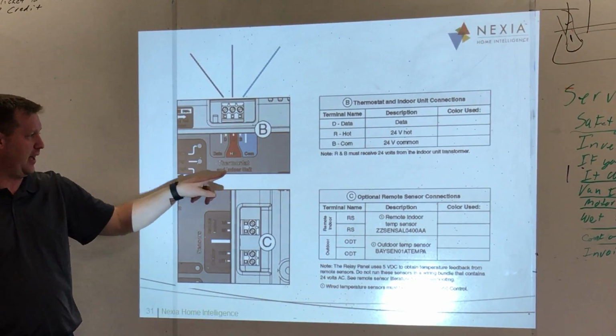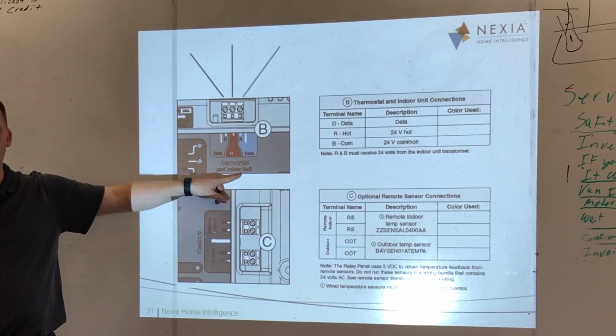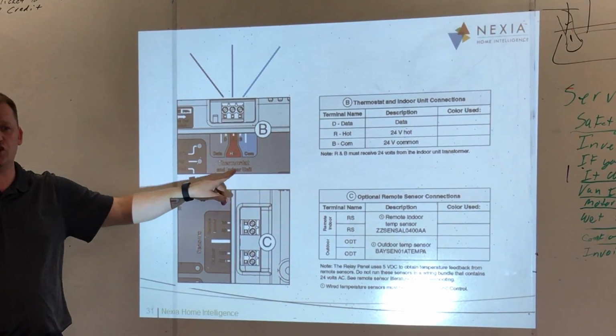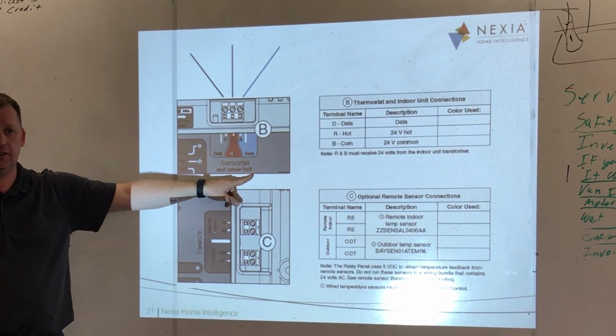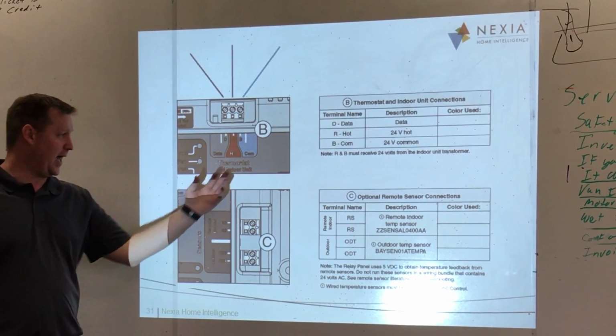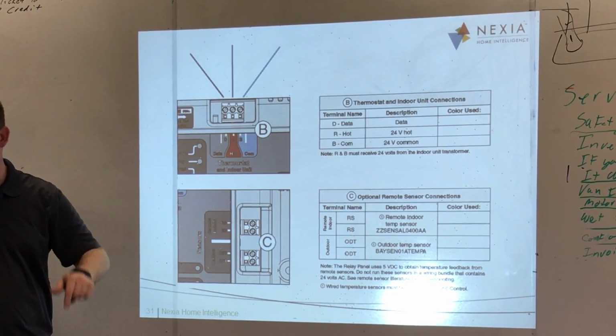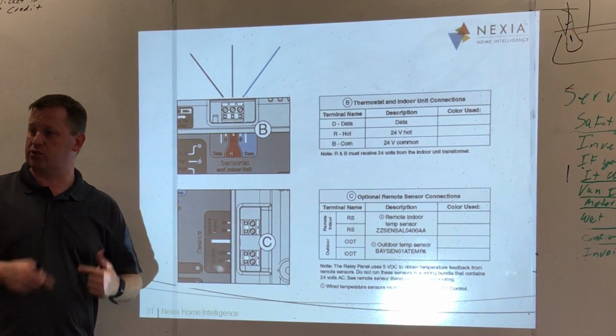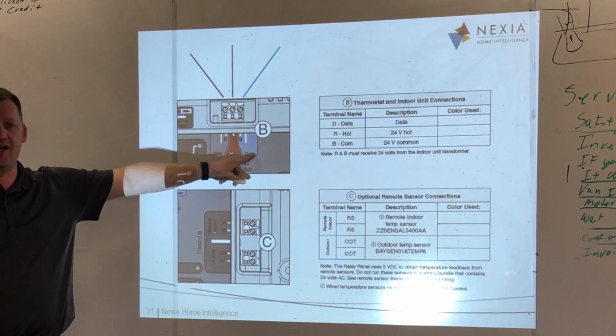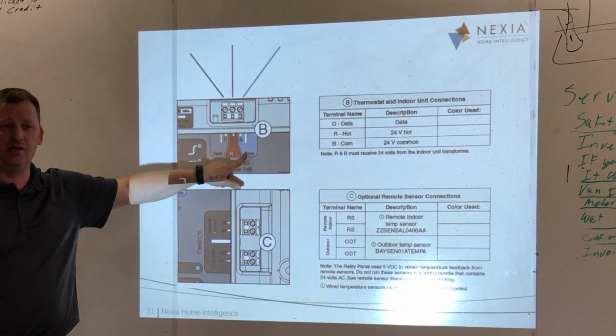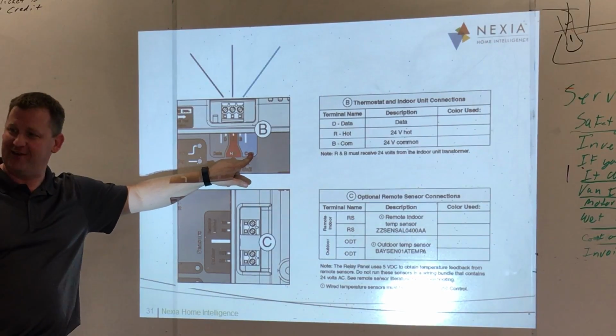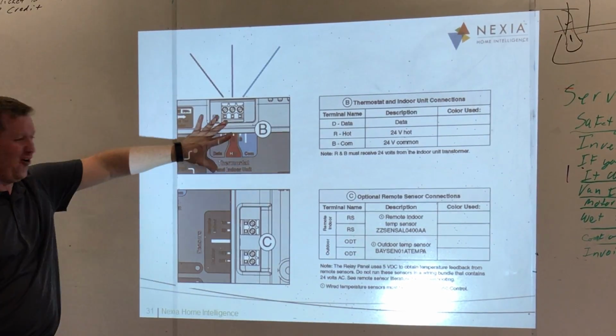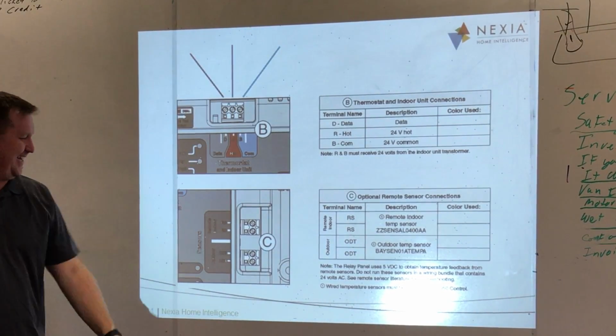So yeah, that's why that's actually changed to indoor unit, and they're talking about changing it to just say 'and equipment,' or add outdoor unit, indoor/outdoor unit. There are these conversations happening at the factory because this is an actual issue. Yes, you do hook indoor unit here, yes, you do hook outdoor unit here, okay, it's the only R&B on this relay panel.